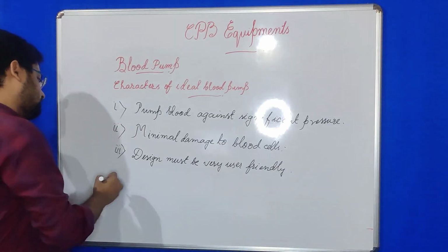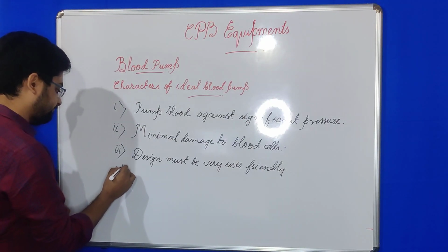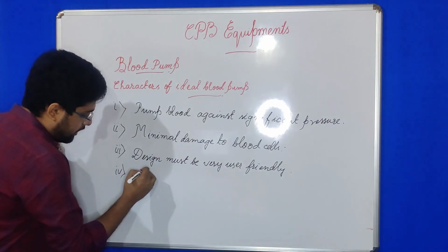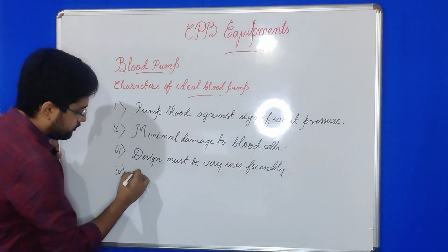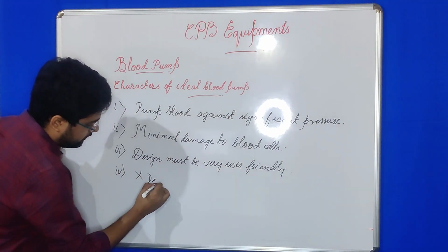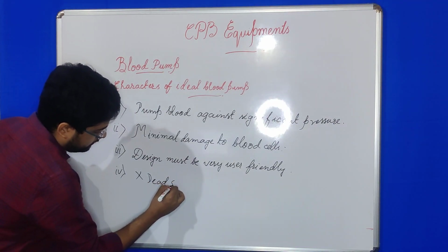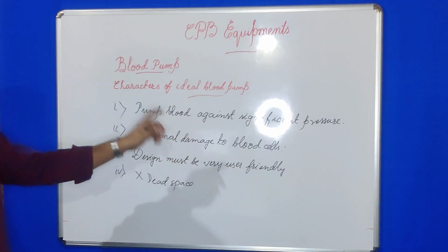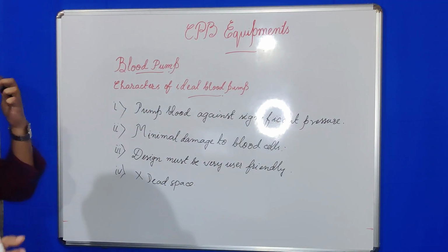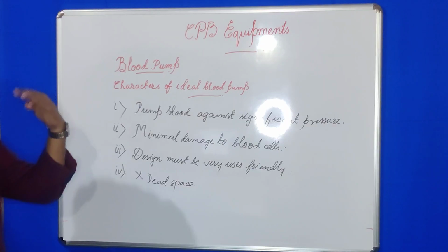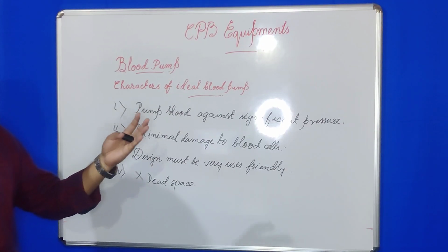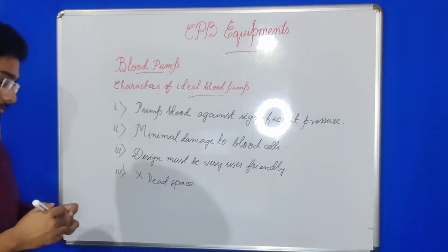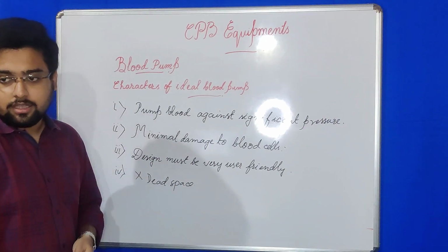It also must lack dead space. There should be no dead space in the blood pump, otherwise our priming volume will be much higher, and higher hemodilution will cause many other complications.